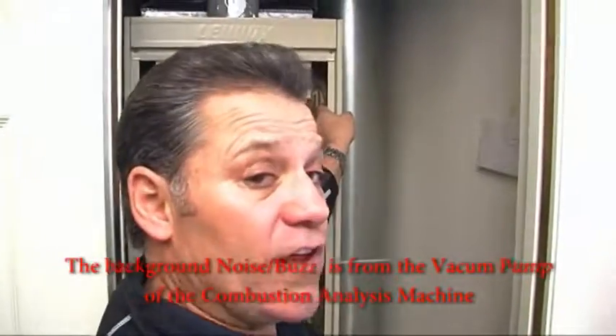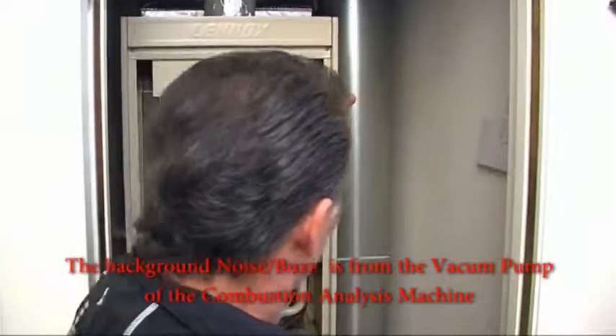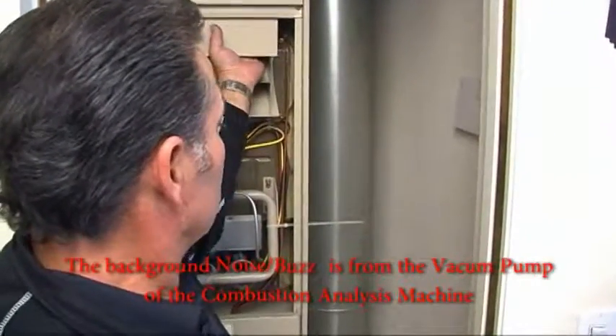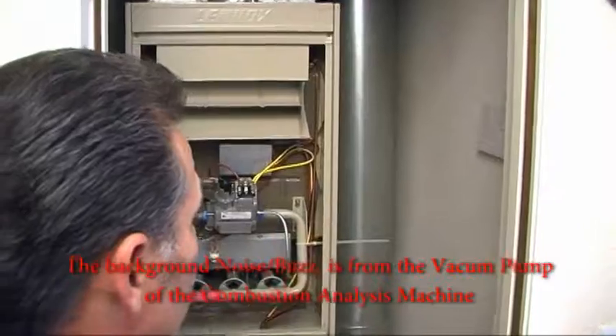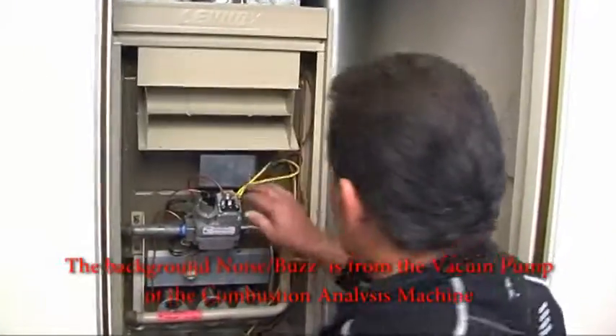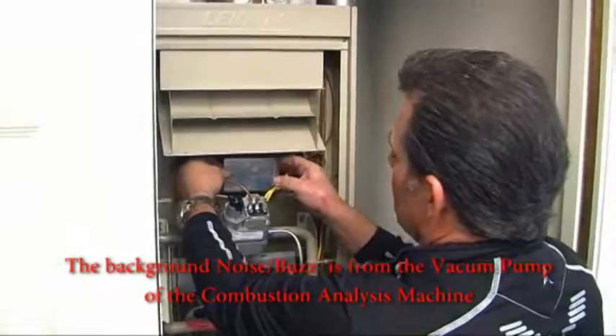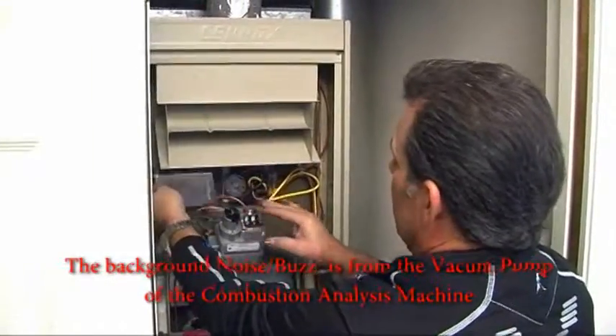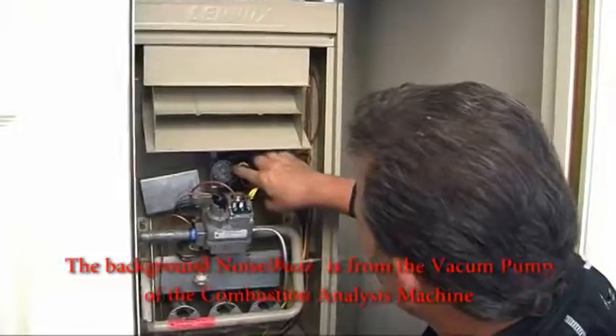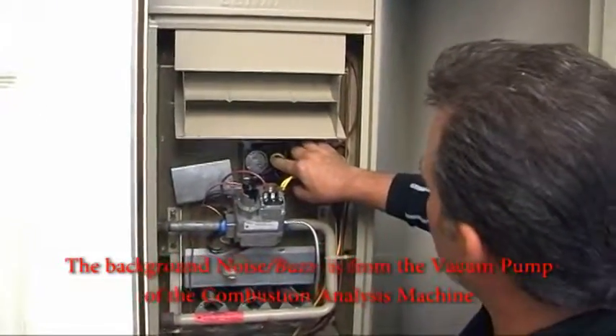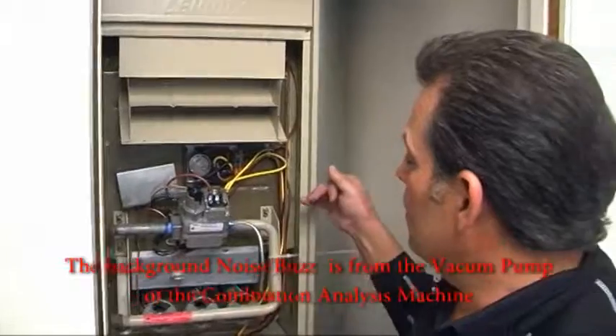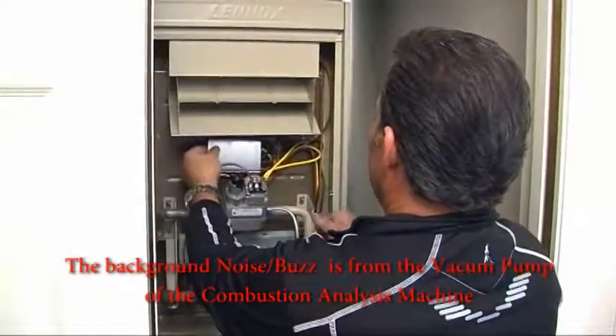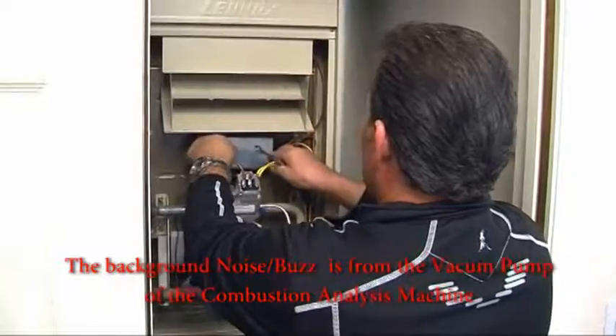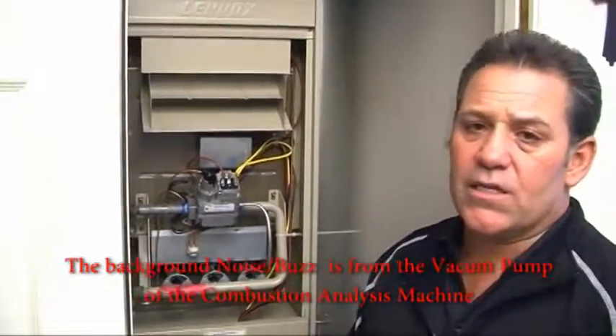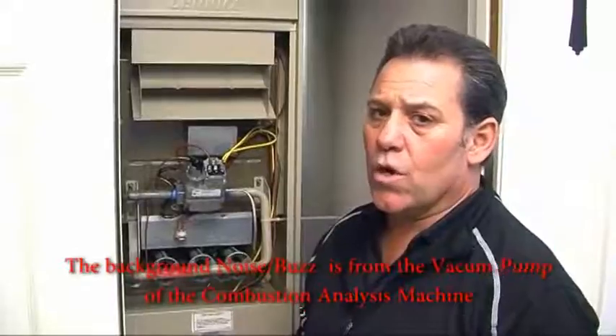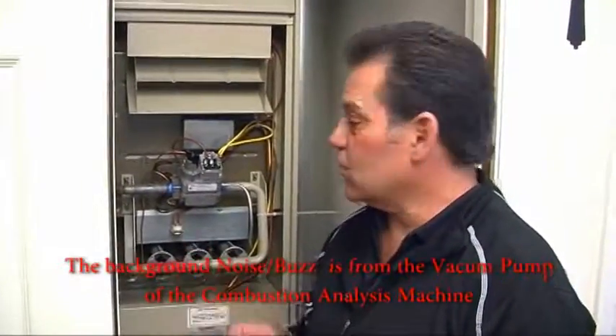Okay, let me show you some of the safeties in this furnace before we leave. Right here on the side, which actually makes contact in here, is my vent safety. Then out of the vent safety comes to my, what I would call the heat exchanger thermostat. This has 2 settings on it, setting at 200 and a setting at 160. That means that when the heat exchanger reaches 200, the fan motor kicks on, and when the thermostat has met temperature, the fan continues to run, and when it comes down to 160, it shuts off.